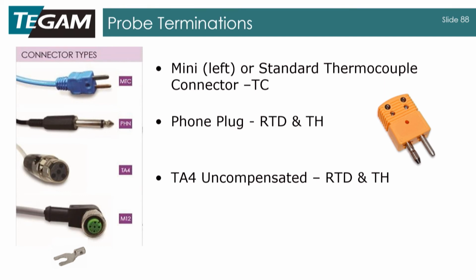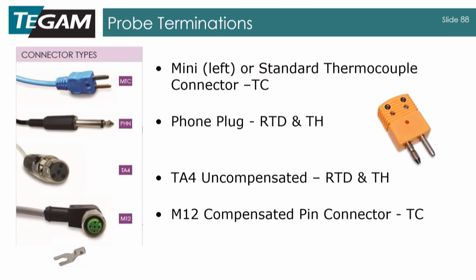The last connector is a little bit of a different one, as it's not used in instrumentation as much as in industry, and it's an industry standard. So what we do is we try to compensate and get in there and work thermocouples in with this connector. So there's two types of M12 connectors. You have a compensated pin connector, and what compensated means is just the opposite. Instead of having a copper connector, this connector is going to have your two dissimilar metals for the thermocouple type that you're using. So if you're going to use this for a thermocouple application, you have to make sure that the M12 connector is made of the same two dissimilar metals as the thermocouple wire you're going to be connecting it to.